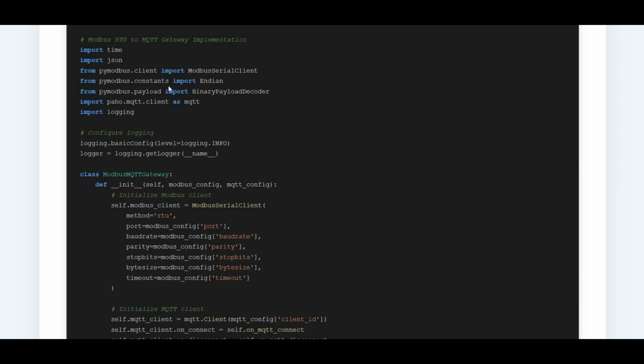Time and JSON are here for scheduling and payload formatting. Then you see PyModbus, which gives us a Modbus serial client for RTU communication. That tells you immediately we are talking to a serial device over RS485, not Internet. The endian import controls byte order, which matters a lot with industrial devices. If you get this wrong, your numbers look fine syntactically but are completely wrong physically. And BinaryPayloadDecoder is what turns raw Modbus registers into meaningful values.